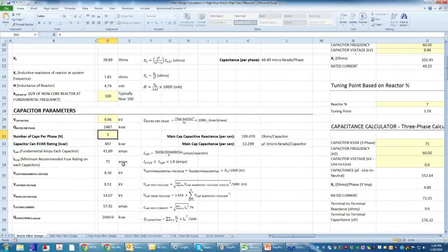Capacitors at the medium voltage level are typically single phase, and since it's an ungrounded bank, they would be 2 bushing capacitors. So in this case, by using 5 capacitors, you can see that there are 5 497 kVar cans per phase. That's what would be the specified value.